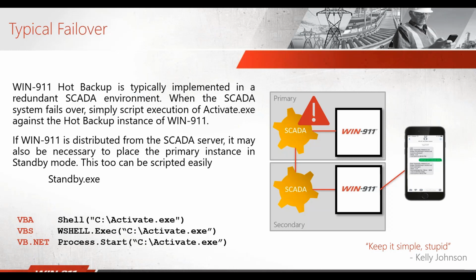So I got a question. The scripting has to be done by the system integrator, is that correct? That's correct, yes. The scripting itself would be done by the system integrator within the SCADA. And what are some ways system integrators have done the hot backup from primary to secondary? Well, like I was saying, typically what our customers like to do is have Win911 follow the failover of the SCADA system. So if the SCADA system fails over, you can run a script within the SCADA that runs this executable, which keeps Win911 in sync with what the SCADA system is doing.